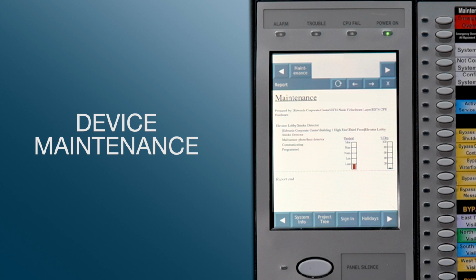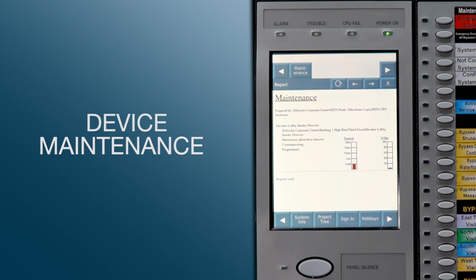The detector electronically compensates for the dirt buildup inside the detector. Since this is an electronic compensation, the range is determined from 0 to 100% of its capabilities. This detector is showing about 3 to 4%, so there's still quite a bit of compensation range available. At 80%, the detector will report a monitor condition for the detector being dirty. At 100%, the detector reports a trouble condition, indicating that the detector needs to be cleaned or replaced.